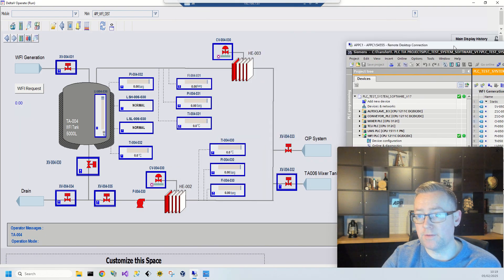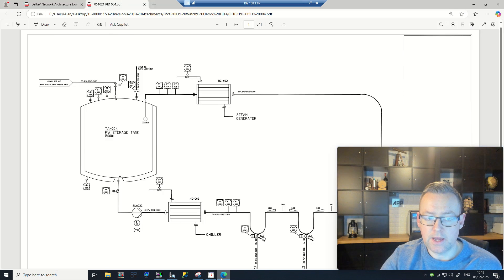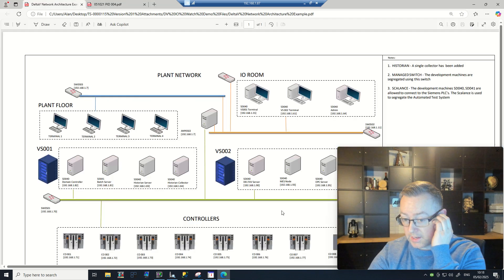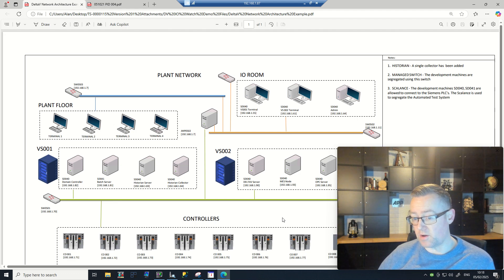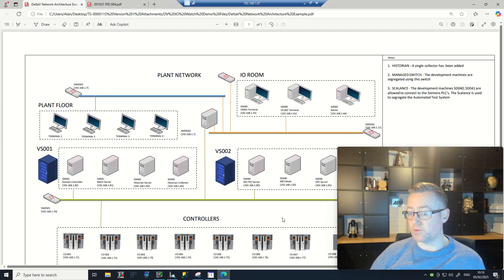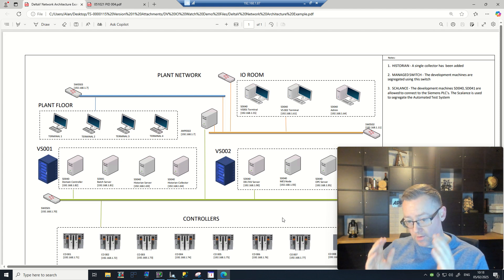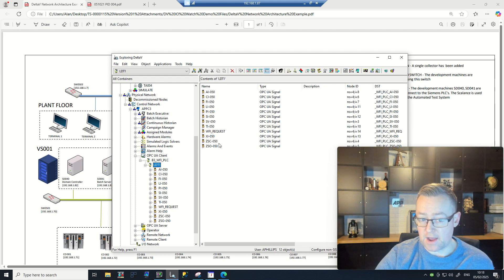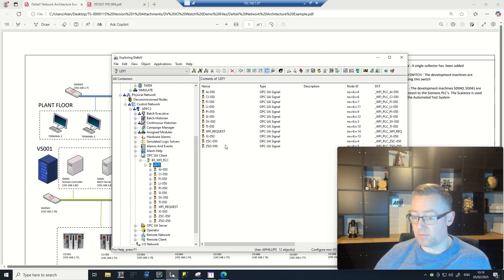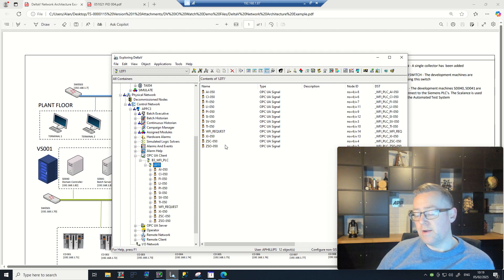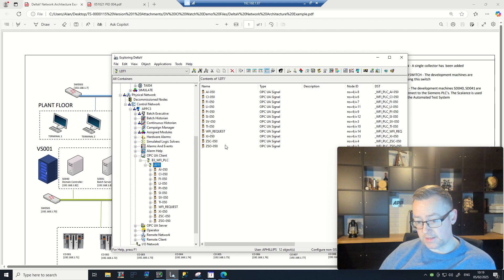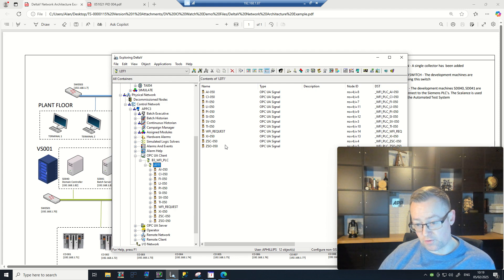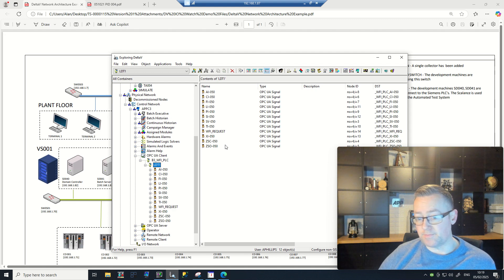So that's an example where, in situations where you have a PLC with an OPC UA server on it, this is by far the most elegant route to take. You've got direct communications right there, and you can set up all your individual devices if they have OPC UA capability — especially for vendor packages. The S7-1500 and 1200 have had this capability for years, and several models of CompactLogix and ControlLogix have this functionality as well. I think this is definitely the way to go.